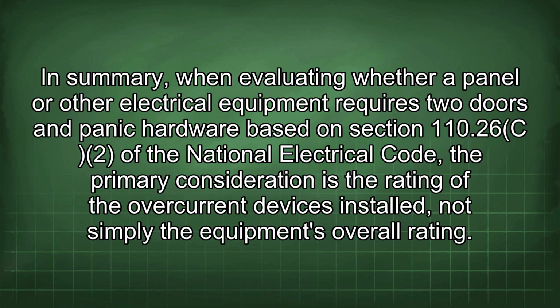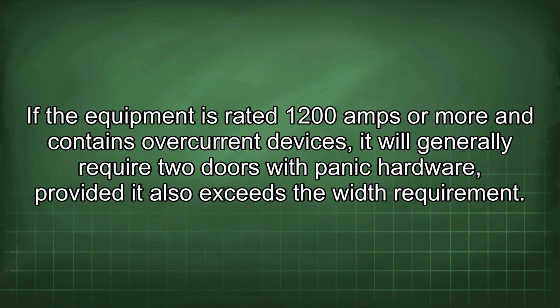In summary, when evaluating whether a panel or other electrical equipment requires two doors and panic hardware based on section 110.26C2 of the National Electrical Code, the primary consideration is the rating of the overcurrent devices installed, not simply the equipment's overall rating. If the equipment is rated 1200 amps or more and contains overcurrent devices, it will generally require two doors with panic hardware, provided it also exceeds the width requirement.